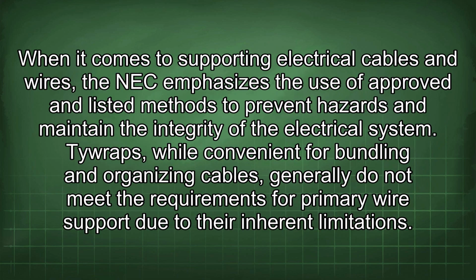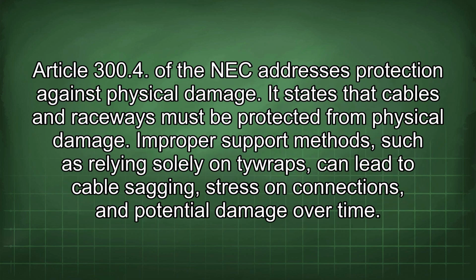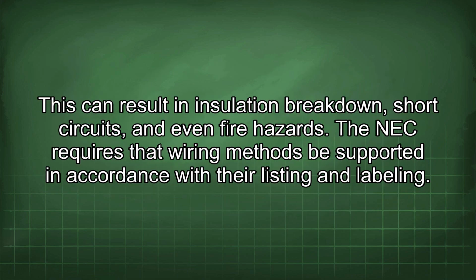When it comes to supporting electrical cables and wires, the NEC emphasizes the use of approved and listed methods to prevent hazards and maintain the integrity of the electrical system. Tywraps, while convenient for bundling and organizing cables, generally do not meet the requirements for primary wire support due to their inherent limitations. Article 300.4 of the NEC addresses protection against physical damage, stating that cables and raceways must be protected from physical damage. Improper support methods, such as relying solely on Tywraps, can lead to cable sagging, stress on connections, and potential damage over time. This can result in insulation breakdown, short circuits, and even fire hazards.